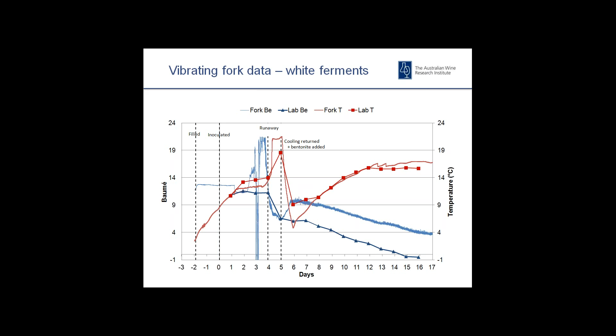just to confuse things on this graph, but in this area here between day 4 and day 5, things started to settle down, and we got both sensors, the vibrating fork sensor measuring at a similar level to the reference Baume. And then from that point we see a bit of a divergence, so that signal from the fork jumps up, and we've got in the region of a 4 Baume offset between the fork measurement and the reference measurement itself. And we believe this is due to the fact that bentonite was added to the ferment tank at that point, and our assumption is that some of the bentonite actually settled on the fork of the sensor, and that damped the oscillation, therefore providing this offset. So essentially we're overestimating the level of Baume in the vessel, and we saw this pattern fairly consistently with the white ferments at Petaluma.